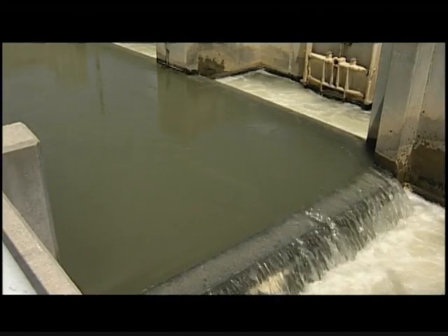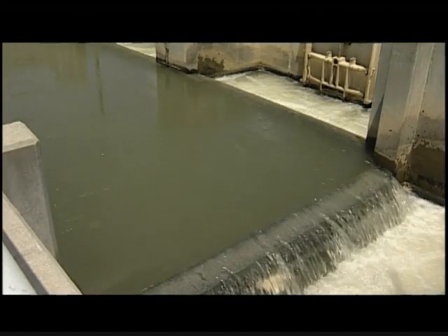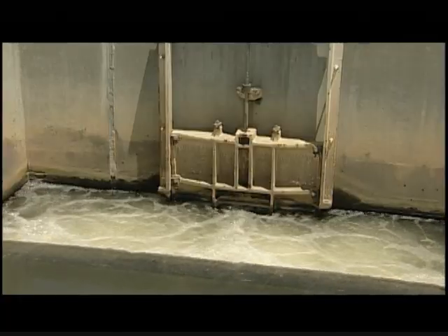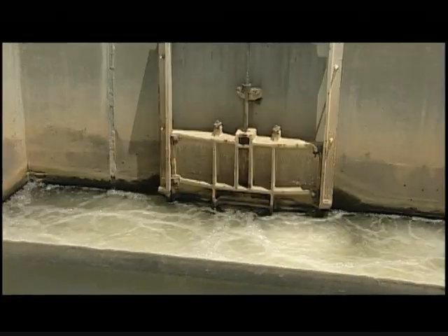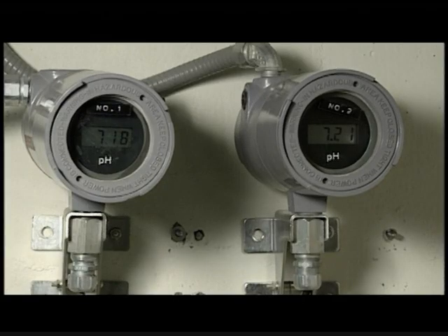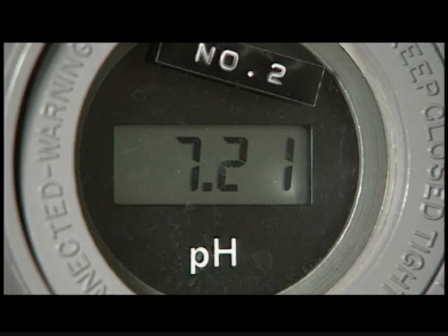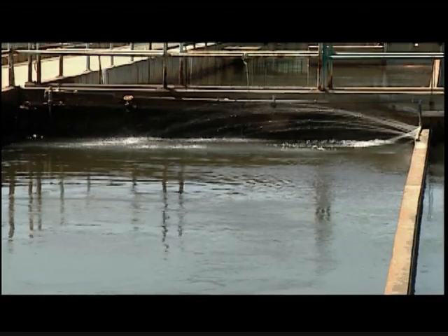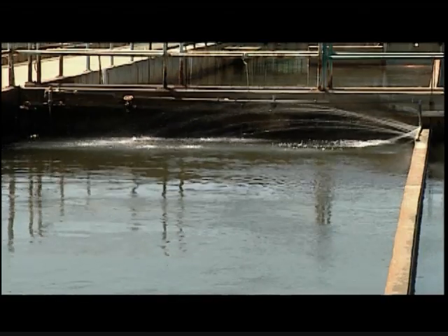Water temperature, for example. Colder water usually slows coagulation and flocculation reactions, which may require more time to achieve optimal floc formation. Extreme values of pH, high or low, will also interfere with the process. Coagulant effectiveness is highly dependent on pH.